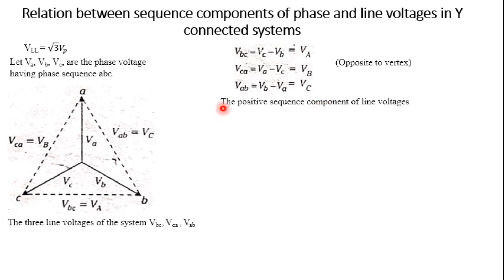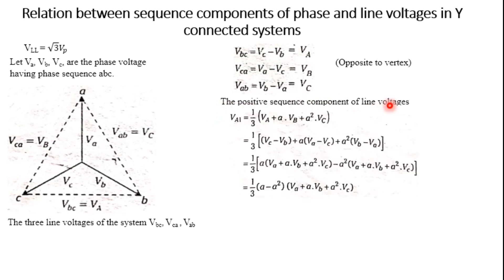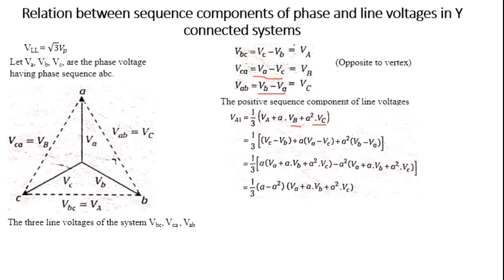For the positive sequence component of the line voltage, do not get confused here. We know the equation: VA1 = (1/3)(VA + A·VB + A²·VC). Now VA can be written as VBC which is VC minus VB; A·VB can be written as VA minus VC; and A²·VC can be written as VB minus VA. Substitute and simplify.